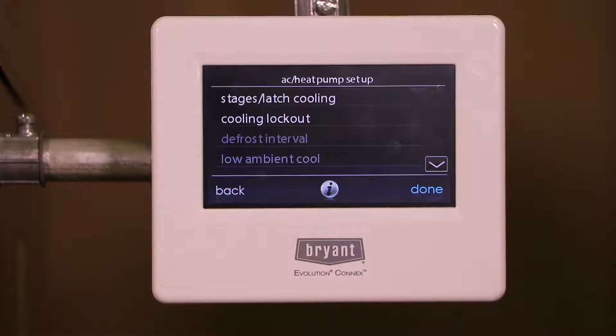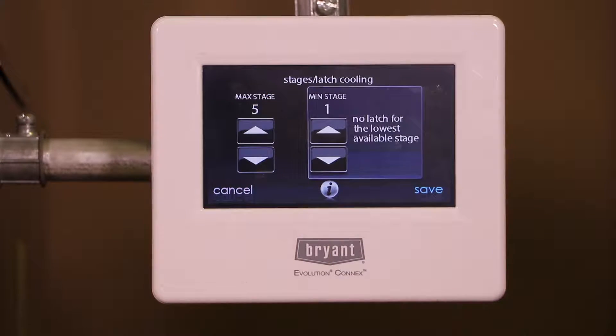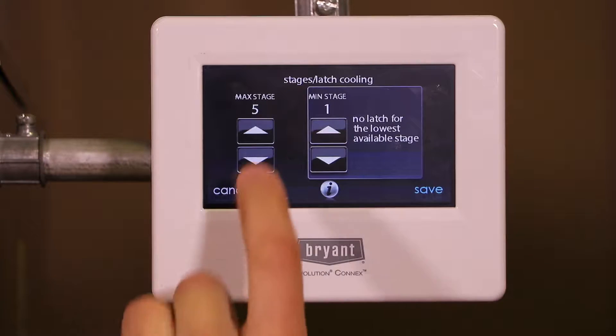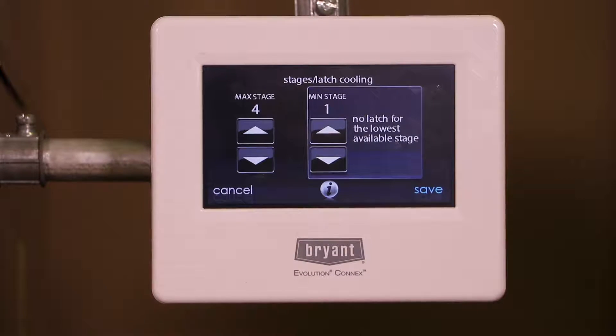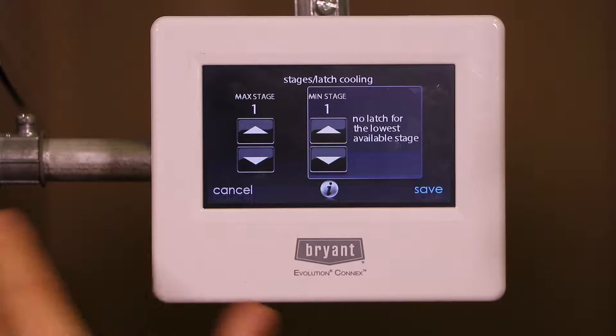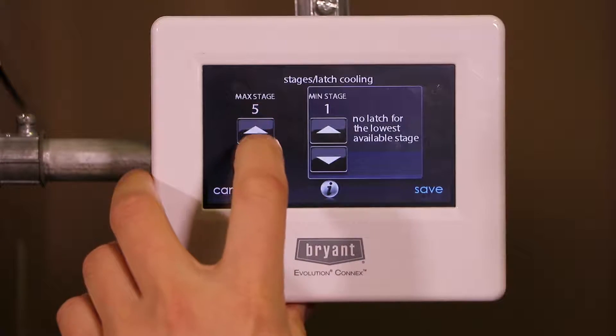In our particular case today we are attached to a five stage air conditioner. In a little while we will attach to a variable stage heat pump and show you what both of those screens look like because they are slightly different. The very first option under here is stages/latch cooling. The first thing is the maximum number of stages. It's a five stage unit, but if for some reason it wasn't perfectly sized right, I may want to bump it down and make it a four stage unit only because maybe the fifth stage is too much capacity for my particular project. I have flexibility of that.